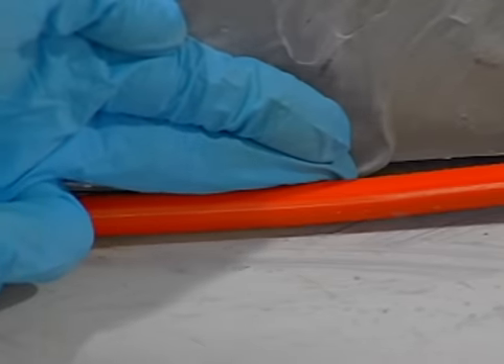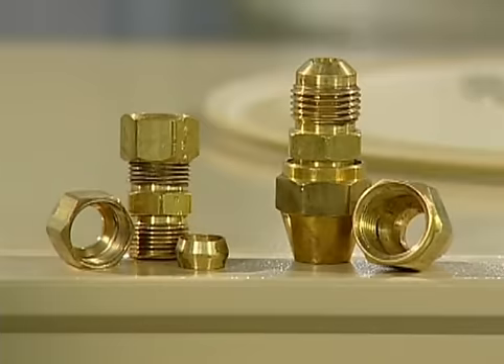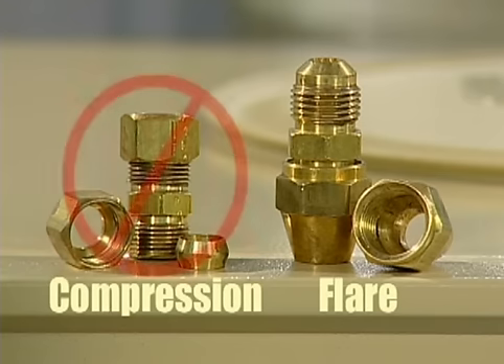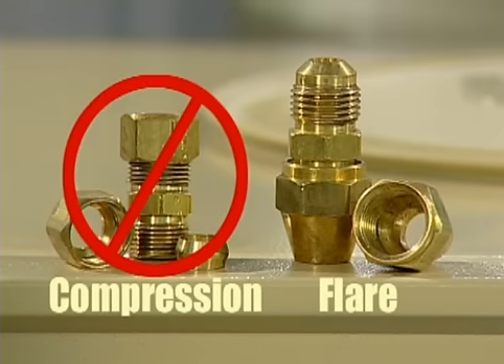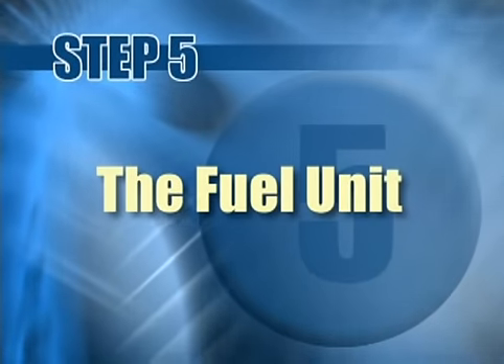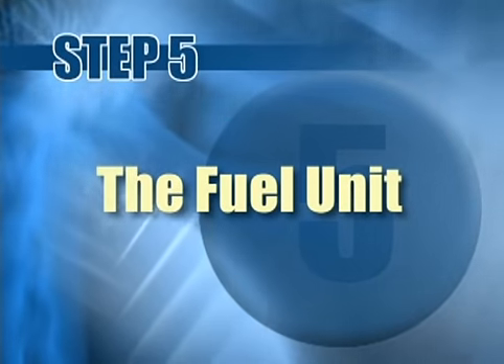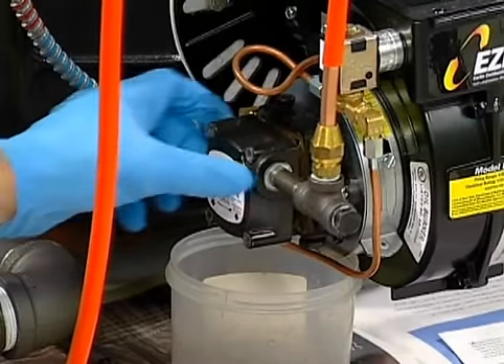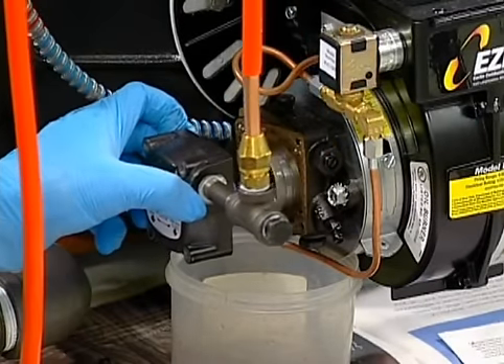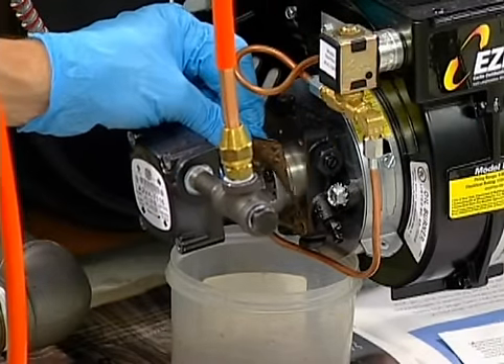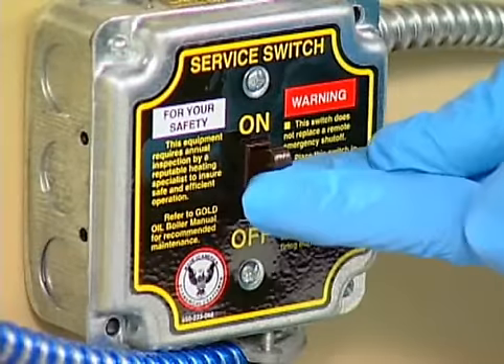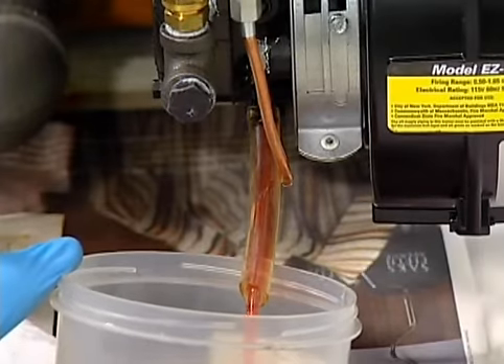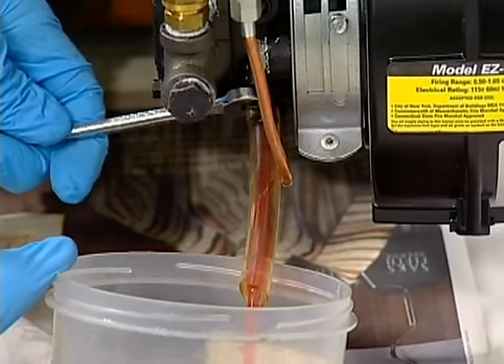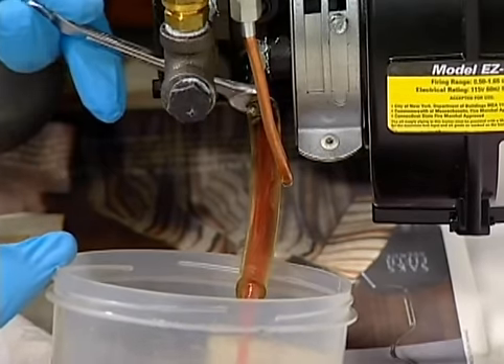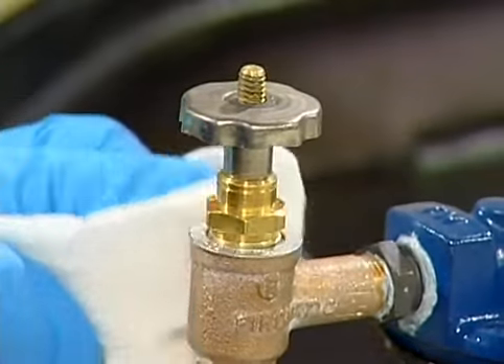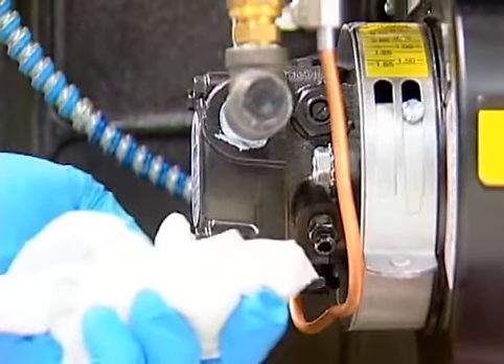Inspect the oil line for kinks or dents. Check to be sure there are no compression fittings. If you find any, replace them with flare fittings. Clean or replace the pump strainer, carefully scraping off the old gasket before installing a new one. Open the valve, turn on the switch, and bleed the unit. Run oil through a clear tube into a container until there are no visible air bubbles. Check for leaks at the valve stem, filter, and the pump gasket.